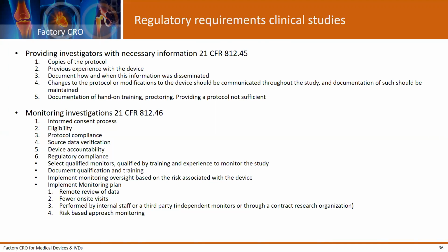You should always provide the investigators with the necessary information, like copies of the protocol, but also documentation of the training and the proctoring. Just providing them with a protocol is not sufficient. You should monitor your clinical investigation, which means the actual data collected should be checked with the patient medical records.